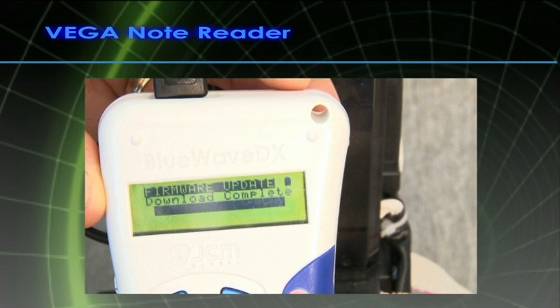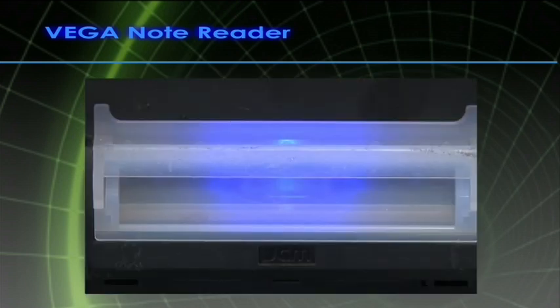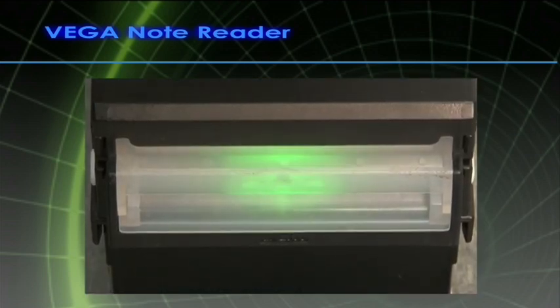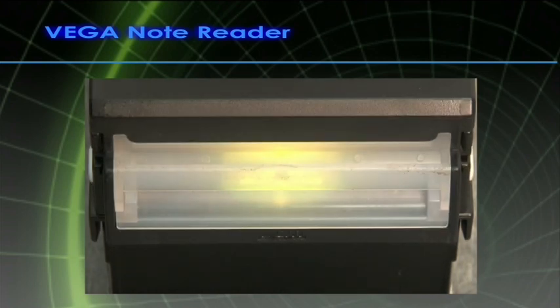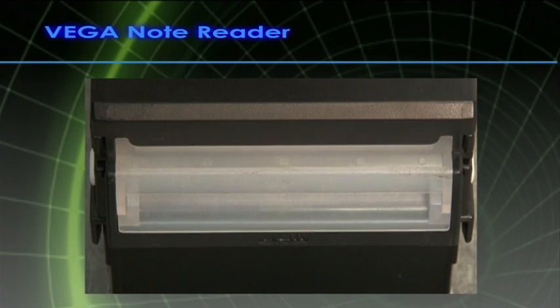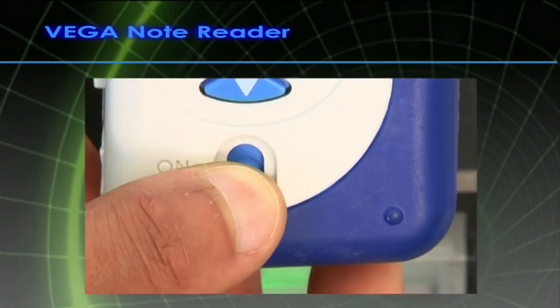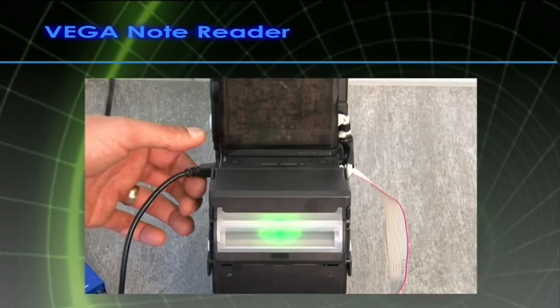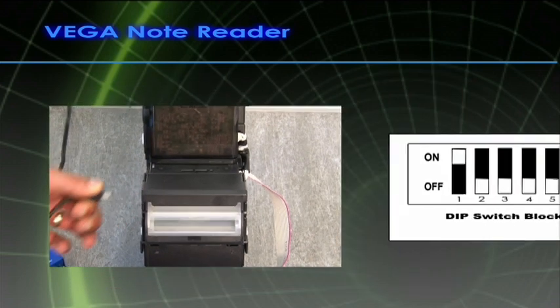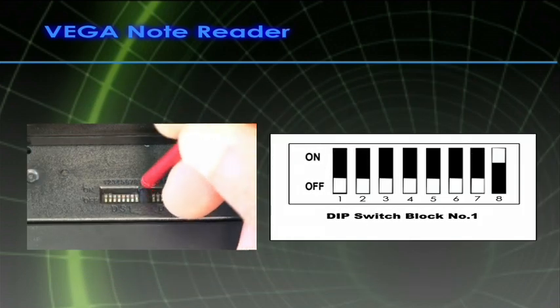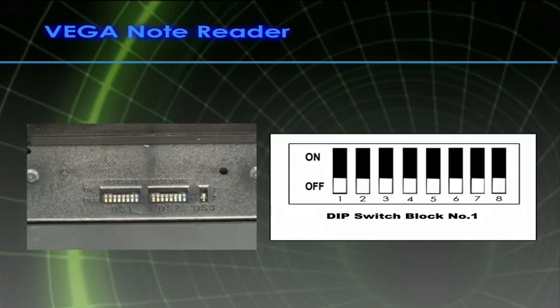The Vega bezel LED will show a blue light for a short while before switching to a flashing green light. The green light will change to yellow during the download process before returning to flashing green once the download is complete. Switch off the Blue Wave DX and disconnect the USB cable from the Vega note reader. Make sure to change the dip switch block number 1 to the original settings.